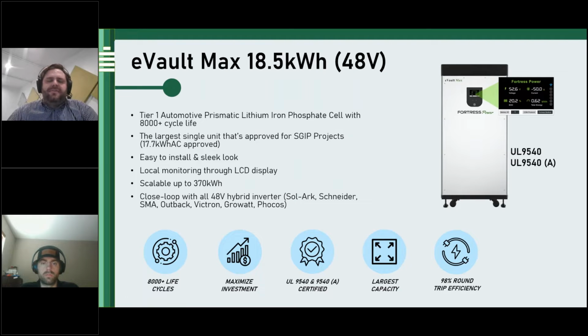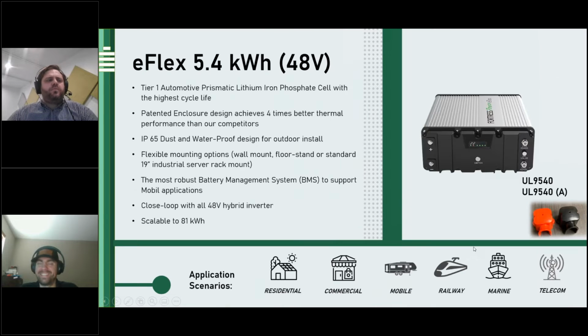So it is real fun to start jacking up your project dollars by selling a very large battery bank, and with the safety of 48 volts, the eVault Max can deliver that up to 370 kilowatt hours, commonly paired with 9 Sol-Arks, which will give you about 81 kW of battery output capacity at this time. That can change with Sol-Ark's product roadmap as well.